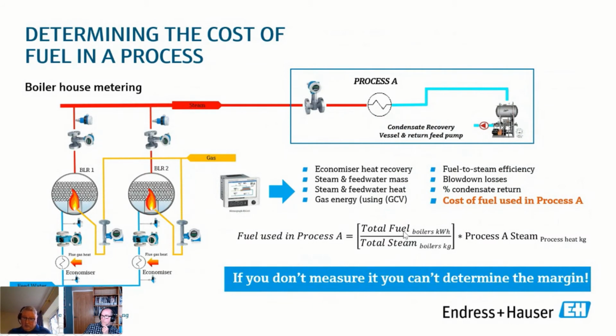So it's the total fuel divided by the total steam, multiplied by just the steam in that process. Now, it makes no sense when you're just looking at one process and a boiler, because obviously this steam is the same as that steam. But imagine, like before, we had two processes. If you measure the steam separately, it's all about the units, because the kilograms cancel, so you're left with a calculation for that fuel, and it's in kilowatt hours. So the number you get is actually the kilowatt hours of fuel in that process, and you know what the cost of the fuel is, so you can work out the cost of heating that.